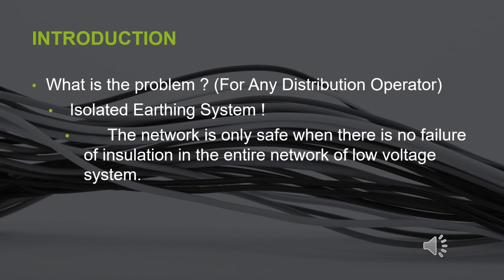As an introduction, we will ask the question, what is the problem? The problem is the isolated earthing system of the Gupan Electric Corporation. The network is only safe when there is no failure of insulation in the entire low voltage network. In the event of only one point of insulation failure in the entire network, the system is unintentionally converted to a line-to-ground network. The next slide will make this clearer.